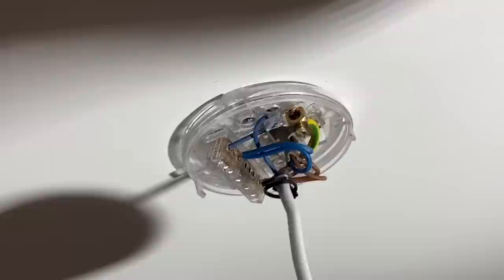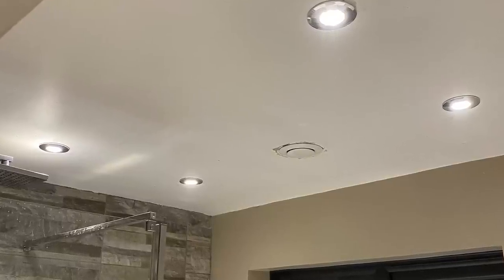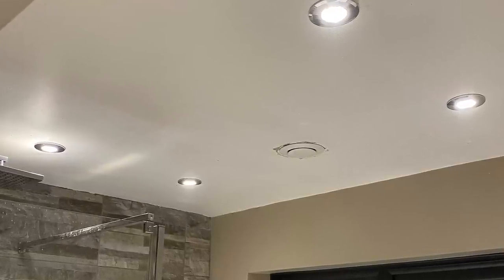So I've got this issue. Where did I end up? In the roof space. On the top floor bathroom it was the downlights. I thought, before I start pulling the downlights down — which can always be tricky — I'll go up top first. In the loft space I was just having a look around and I spotted a joint. Not a junction box — a joint. So there was no box. Some joints just made with Wagos, without a box.